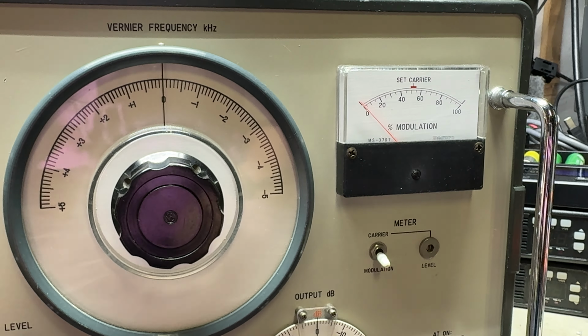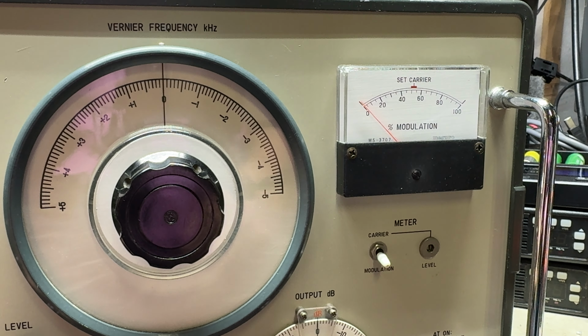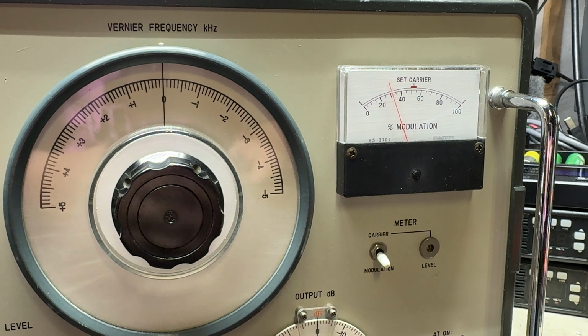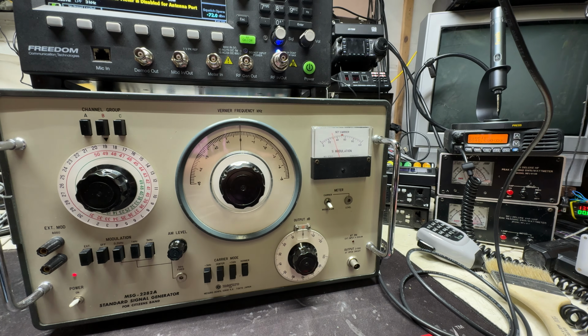I suppose while we're zoomed in, we can check our modulation. So I'll set 1 kilohertz, and we're set to 30, which is exactly where it should be. Now I'm going to take control of it manually, and it'll drop to 0. And we have 20%, 30%, 40%, 50, 60, 70, 80, etc., all the way up to 100 and plus. So normally you just leave it set on the fixed side of the scale, and that gets you the right amount of modulation for really adjusting things in. All right, so that's pretty much it for all of the functions.